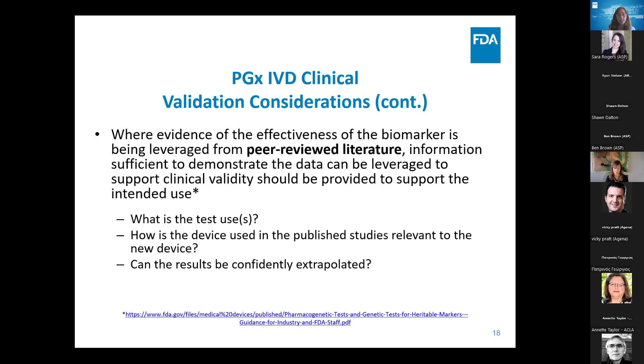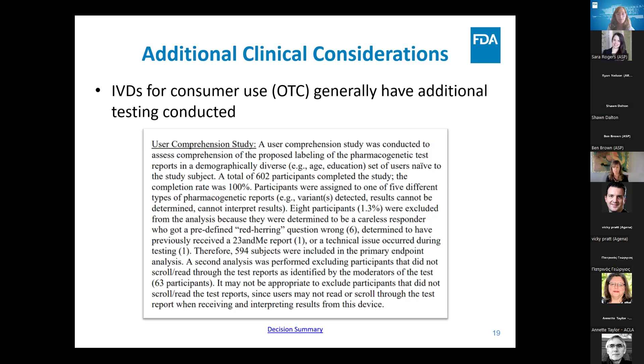And so I do want to also add that IVDs for consumer use or over-the-counter use, including pharmacogenetic IVDs, generally have additional studies conducted to generate data demonstrating that the tests are accurate in the hands of lay users, including sample collection, and that lay users can understand the results. These additional studies are generally user comprehension studies, and we also consider human factors during pre-market review where applicable. But on this slide is an example decision summary excerpt, again, describing a user comprehension study that was required for clearance of a direct-to-consumer pharmacogenetic assessment system pursuant to that device regulation's special controls. So as I mentioned, special controls are tailored to specific device types, and in this case, a user comprehension study was required for authorization.